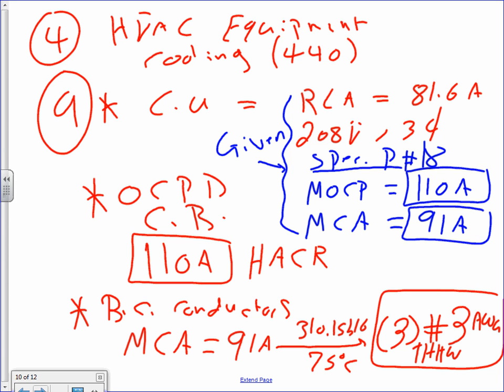Okay, right on the nameplate, you're going to find, guys, maximum overcurrent protection device 110 and minimum circuit ampacity 91. These are on the nameplate of this condensing unit, the chiller, right on the nameplate. Okay, now based on this, can I get you guys to understand these are specs on the nameplate of the cooling unit?